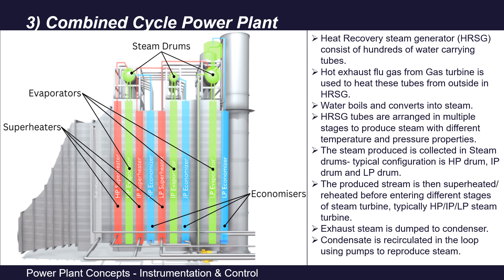The flue gases from the gas turbine exhaust are passed through the heat recovery steam generator (HRSG). The HRSG consists of many — basically hundreds of — water-carrying tubes. Outside the tubes, the hot exhaust flue gases are passed, thus the water gets heated and converted into superheated steam. This superheated steam is then used to rotate the steam turbine blades, which is connected to the generator rotor shaft, and electricity is produced.